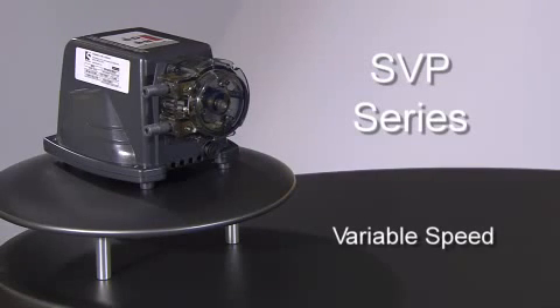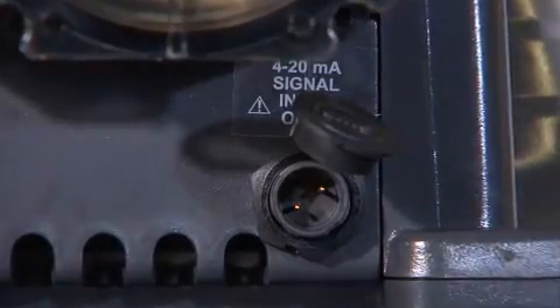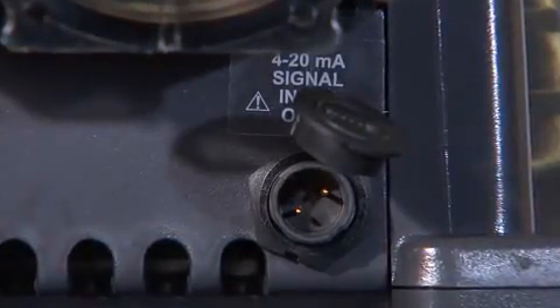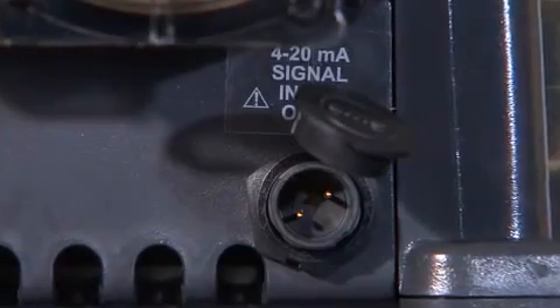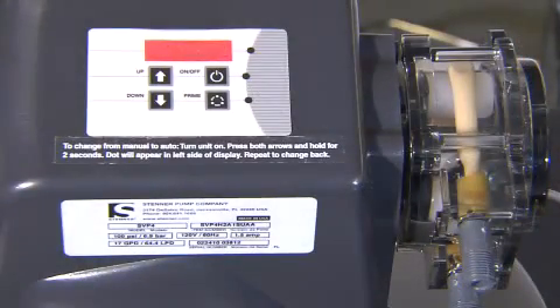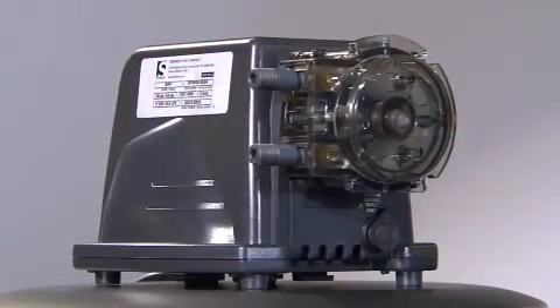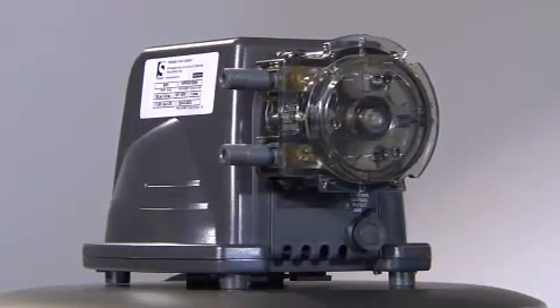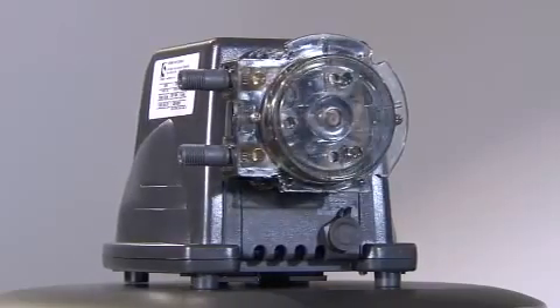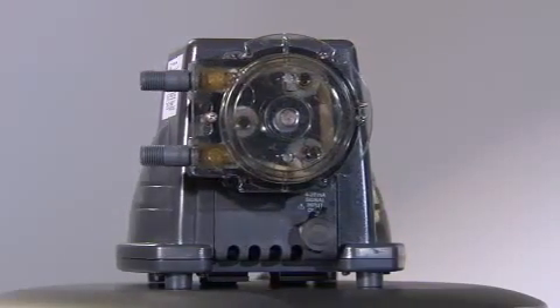The SVP Series is an adjustable variable speed pump with a DC motor utilizing the same pump head as in the Classic Series. The pump can operate in a 4 to 20 milliamp mode to pace the pump. There is an external port to accept an input control signal from analytical measuring devices such as pH or ORP monitors and water meters. The digital control pad allows manual or automatic output control from 5 to 100% in 1% increments. The SVP is used in many applications, such as the injection of acids or caustics to alter pH for treatment of wastewater in manufacturing processes or wastewater facilities.